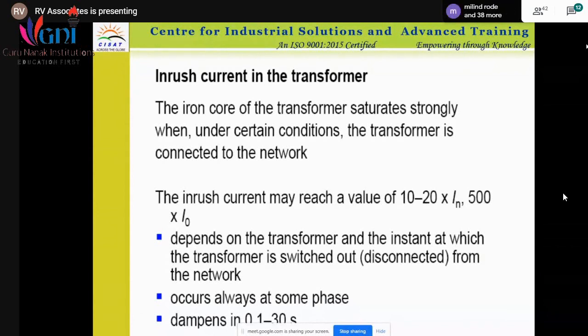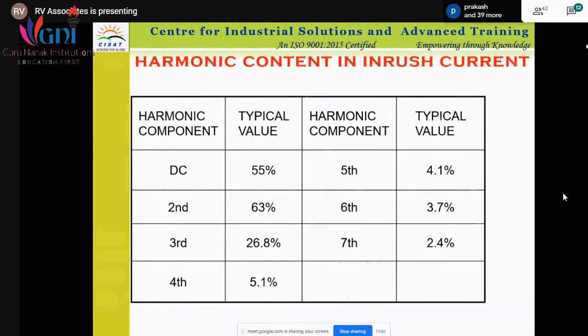So what we say, it's like a second harmonic. Inrush current is nothing but a second harmonic. These are the components of the inrush current. So why would we say that's a harmonic component? The second harmonic component is almost around 63%, and that is to be protected.